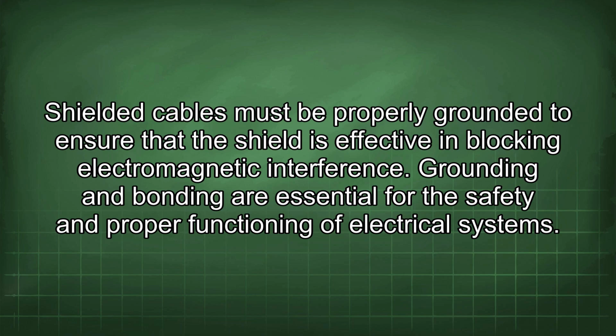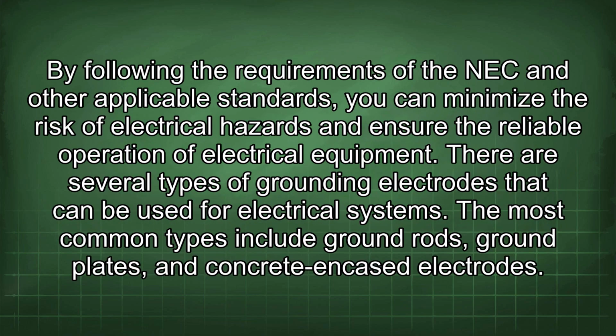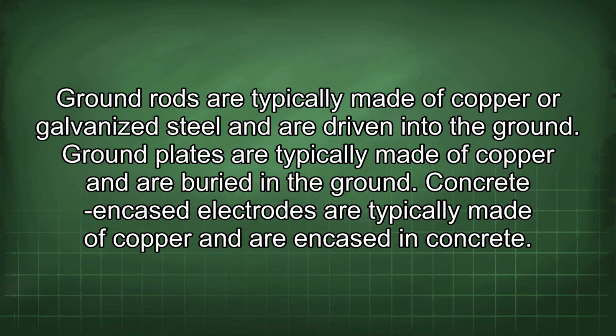Shielded cables must be properly grounded to ensure that the shield is effective in blocking electromagnetic interference. Grounding and bonding are essential for the safety and proper functioning of electrical systems. By following the requirements of the NEC and other applicable standards, you can minimize the risk of electrical hazards and ensure the reliable operation of electrical equipment. There are several types of grounding electrodes that can be used for electrical systems. The most common types include ground rods, ground plates, and concrete encased electrodes. Ground rods are typically made of copper or galvanized steel and are driven into the ground.